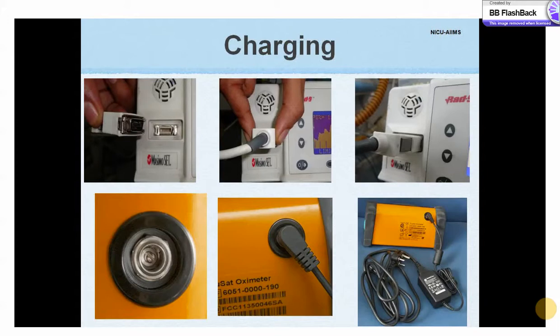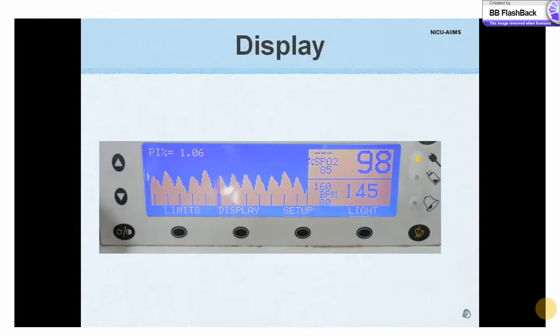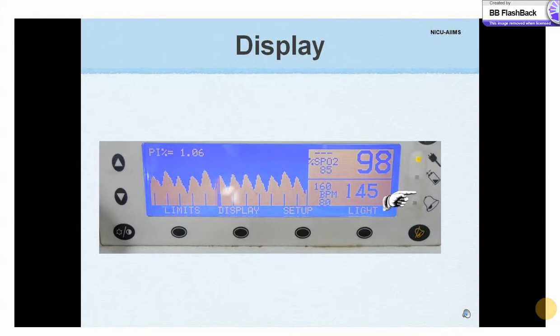Some models have a direct slot for AC power connection. The pulse oximeter should be switched on by pressing the on button at the front panel. This light indicates the connection of the charger, and this light blinks when the battery is running on low charge.